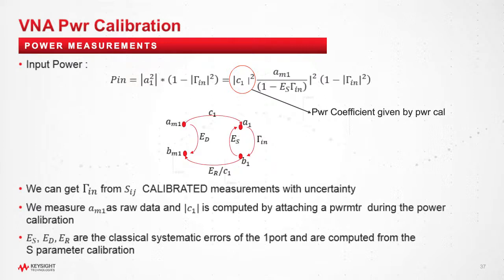Is it correct to state that for current performance network analyzers, the uncertainty on the calibration elements, presumably the standards, is the largest contribution to the overall uncertainty for S parameter measurements? Yes and no. It really depends on the level of the signal that you're talking about. If you have, for example, a filter with a 100 dB stop band, then when you measure the stop band, the noise of the VNA will play a bigger role. But when you measure the parameter within the passband, then definitely the calibration will play the bigger role. So there's no unique answer. It strongly depends on the kind of device that you are measuring. I hope that answers your question, Franz.